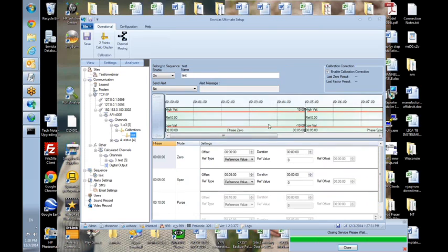And then here is where we would configure the calibration. So we're going to say 03. Actually, we'll say 04, 1. So what it's going to do is zero for 4 minutes, and then it's going to take a 1-minute sample, or a 1-minute average there. And you can see it shows the 0, phase 0, and then where the measurement is here.